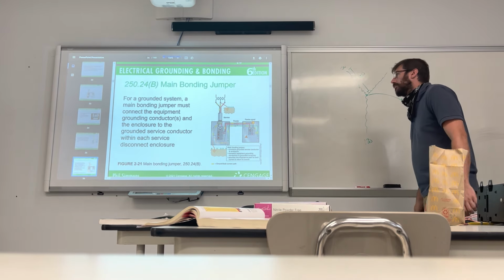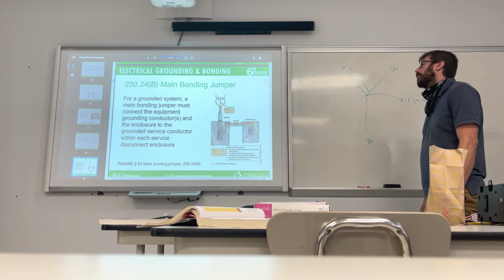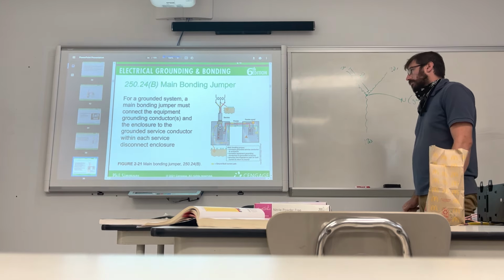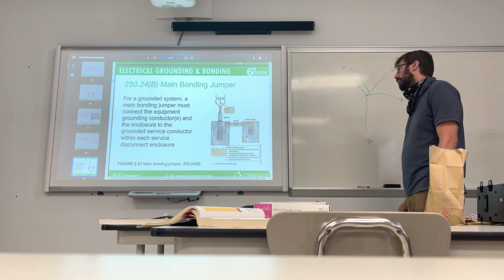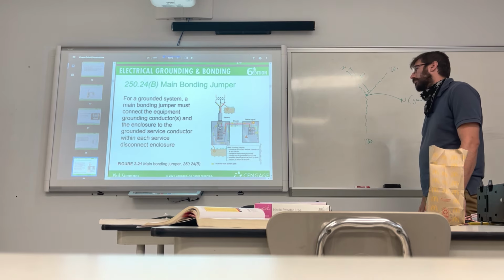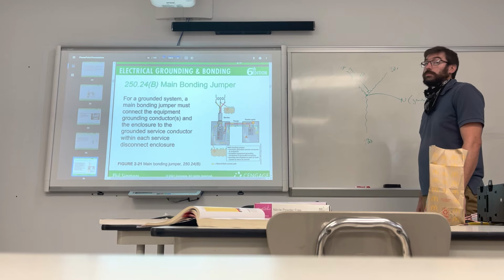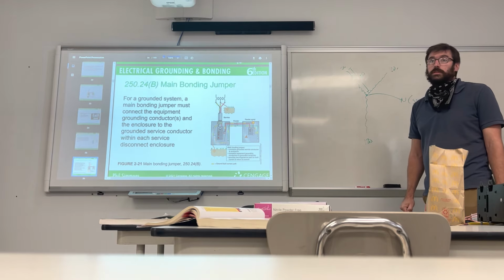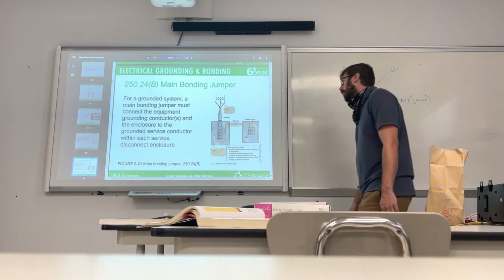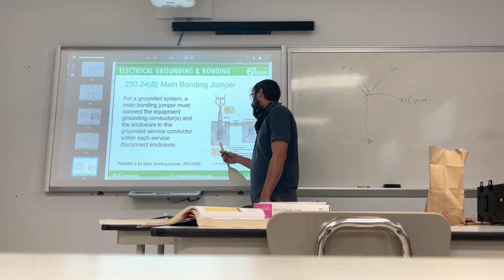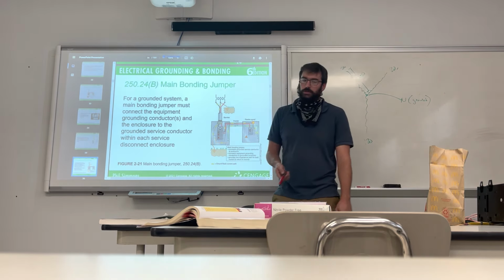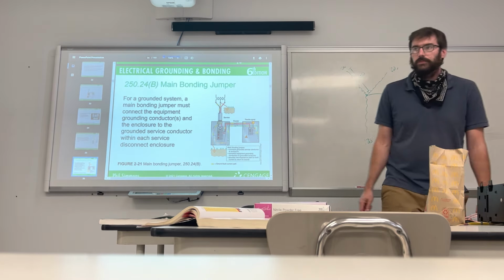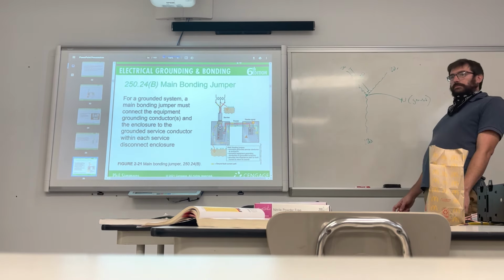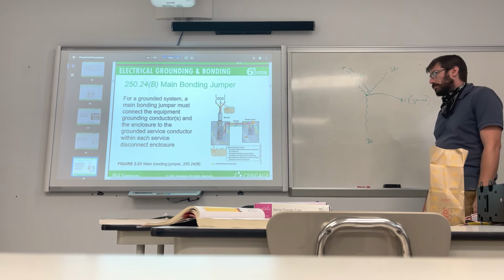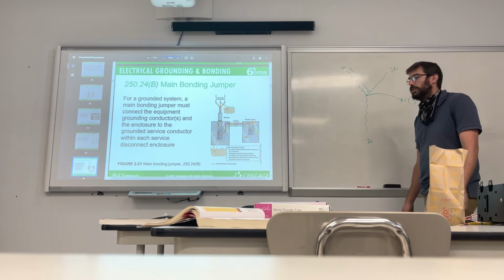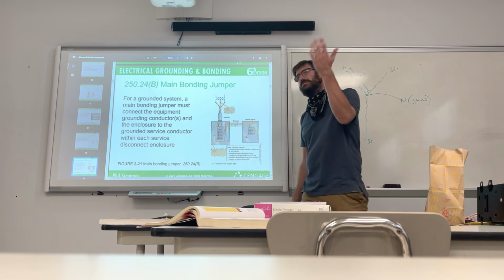Main bonding jumper. For a grounded system, a main bonding jumper must connect the equipment grounding conductors and the enclosure to the grounded service conductor within each service disconnect enclosure. Any new information there? It's like the 31,000th time. But Phil, how thick does that grounding jumper have to be? That bonding jumper? Are you talking like a 200 amp, did you say from before, or just in general? Let's just say in general. How would you explain that to somebody? So how thick should I make that?